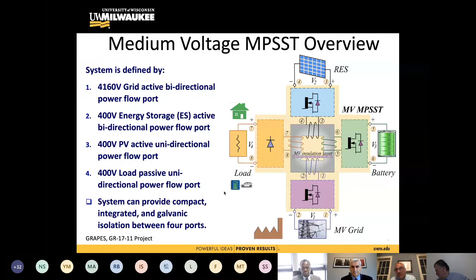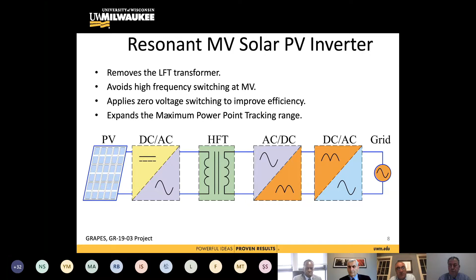Another project that we have been working on for the past couple of years is how you can get solar PV and directly connect it to the medium voltage, and do that by getting rid of the low frequency transformer. So you go up, and on the secondary of the transformer you move the voltage up to medium voltage and then to the grid, rather than putting it at low voltage and using a large transformer to get it to the grid. Isolation is required, electrical isolation, so that is where the transformer is needed.